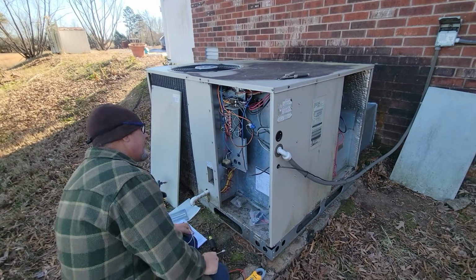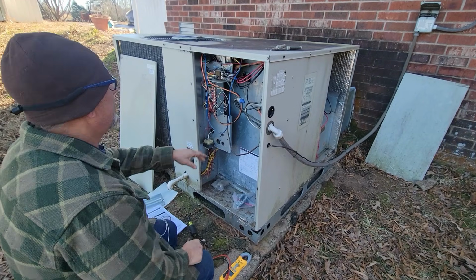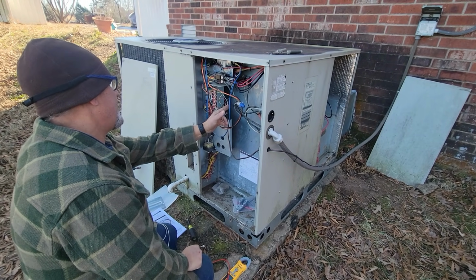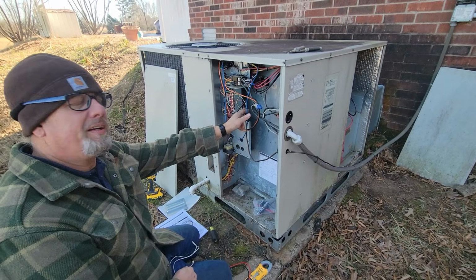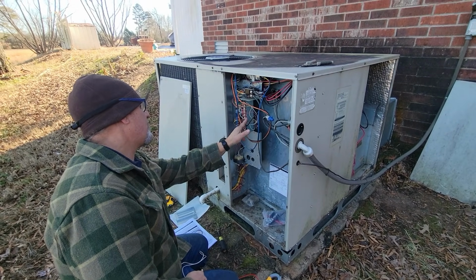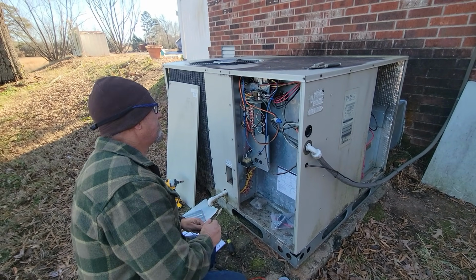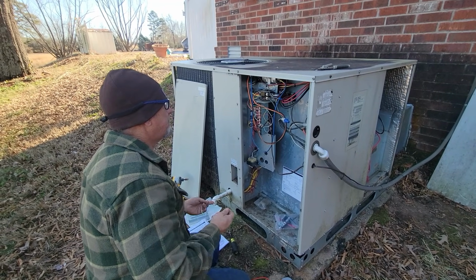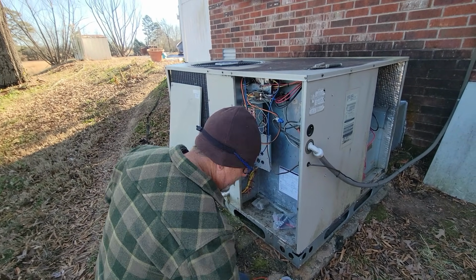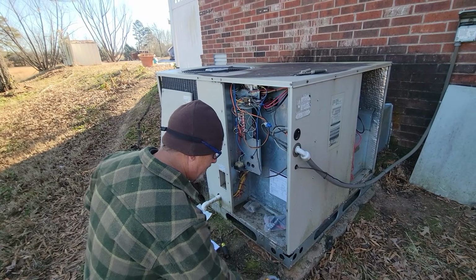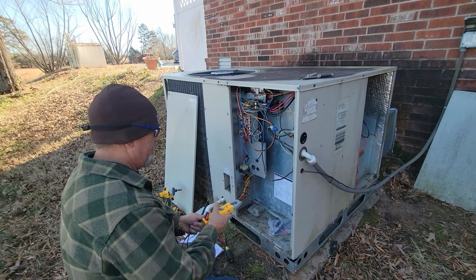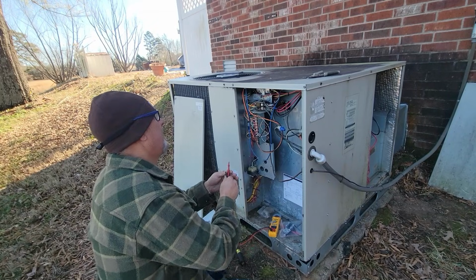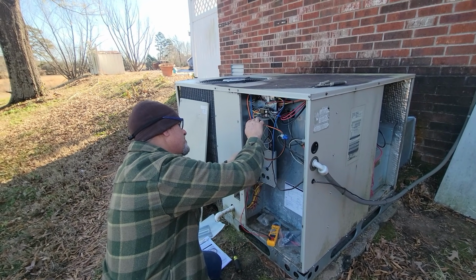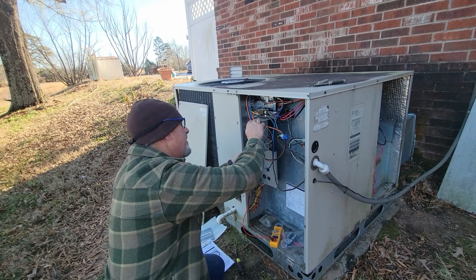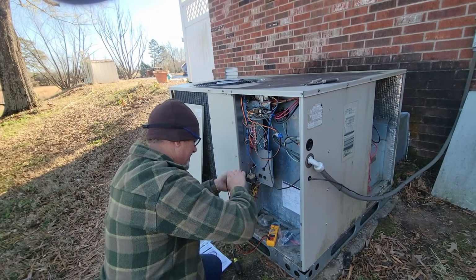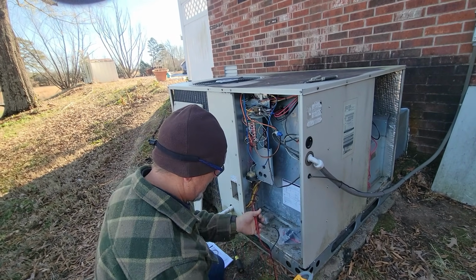But it seems like our heaters from the thermostat, or our second stage from the thermostat, is not calling. Let me double check, we should have 24 volts, but we can give it a minute, right? W2 common, nothing yet. Nothing yet. So we're going to give it a little bit.